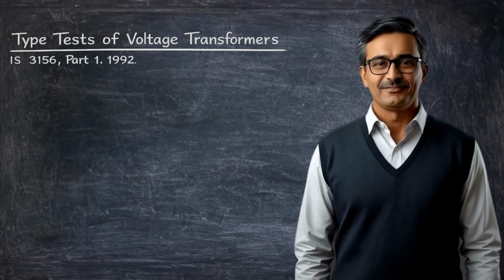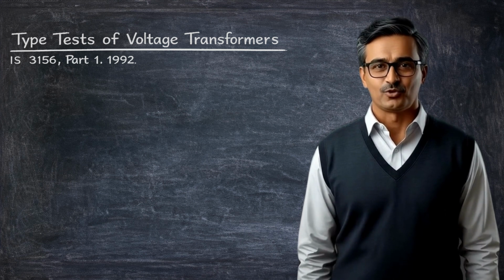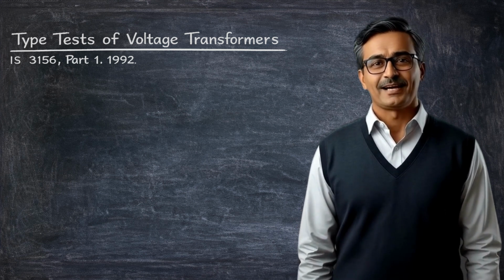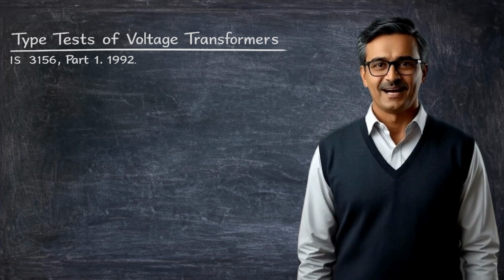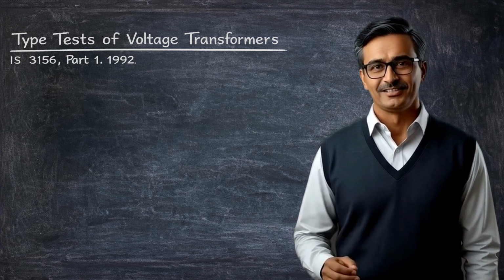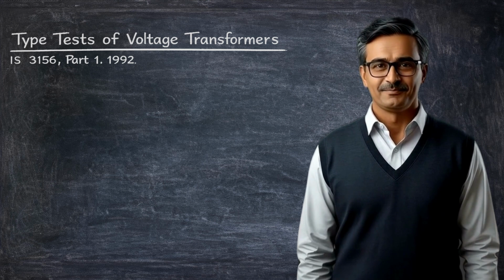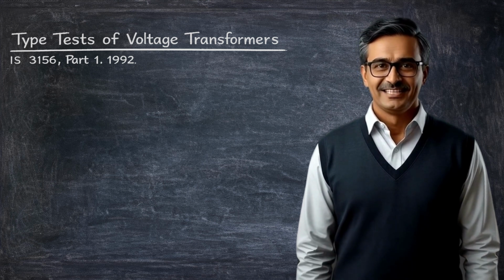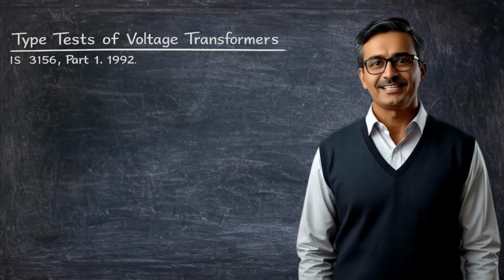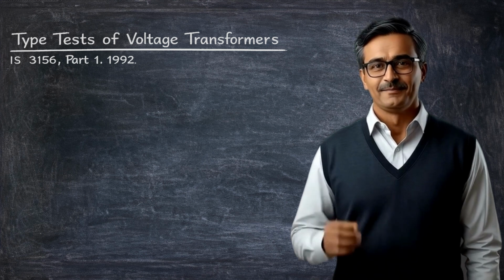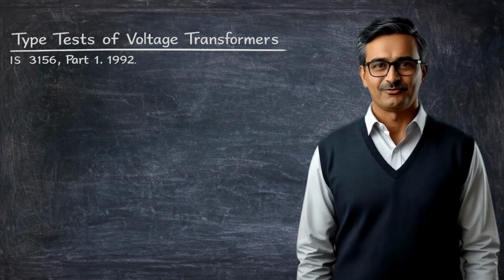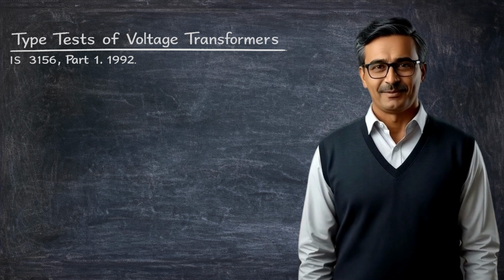Type tests are different from routine tests. Routine tests are performed on every transformer, but type tests are performed only on one sample transformer of a particular design. These tests verify whether the design of the transformer meets the required standards and performance limits. According to the standard, the following tests constitute the type tests.